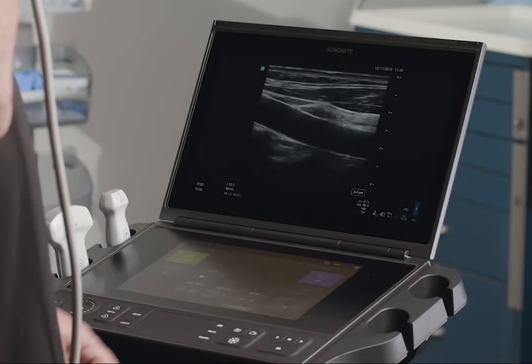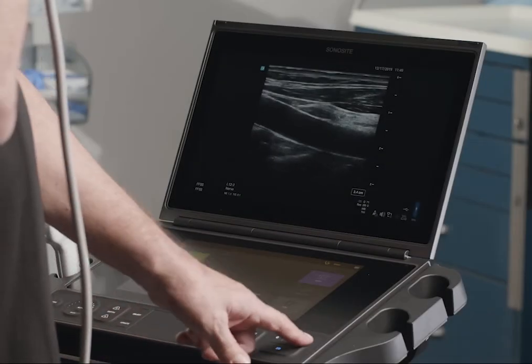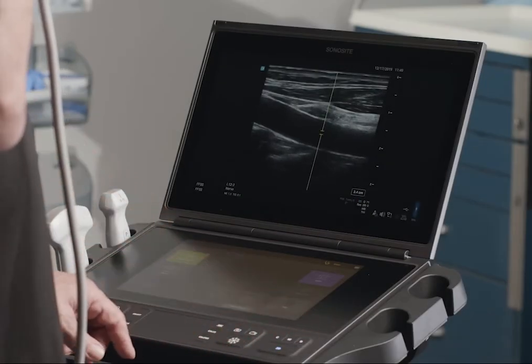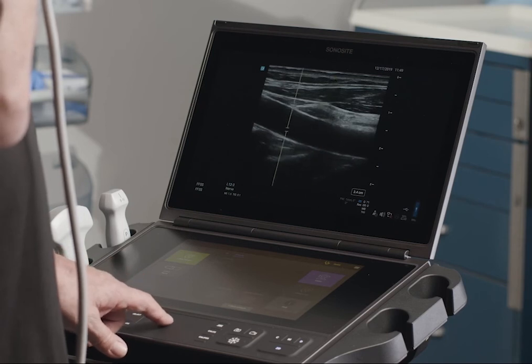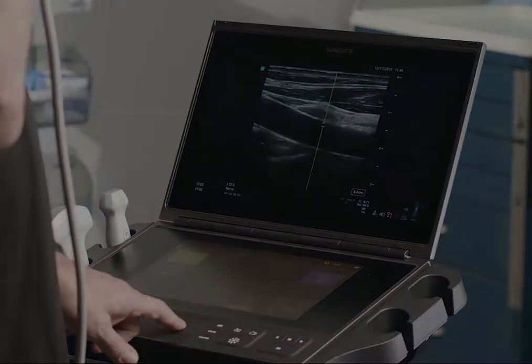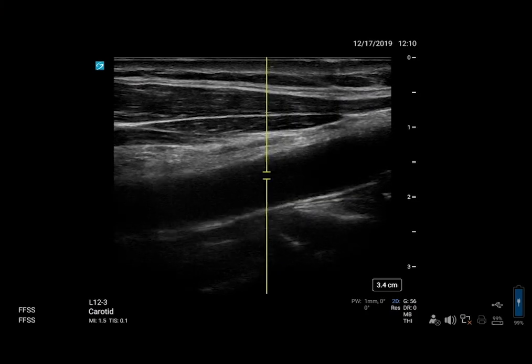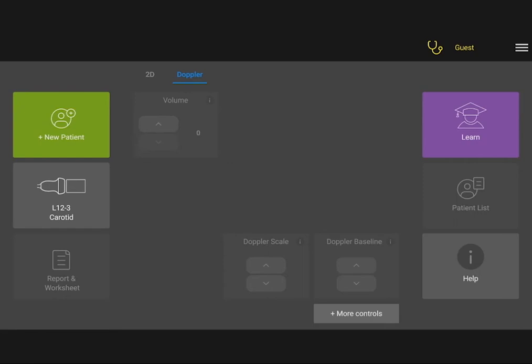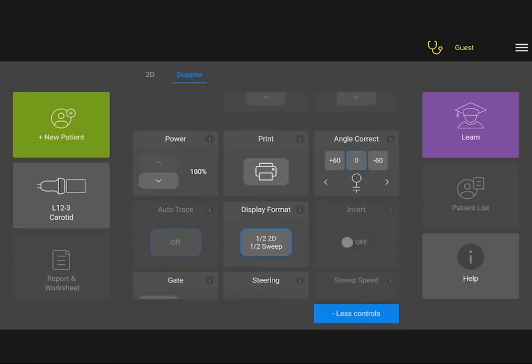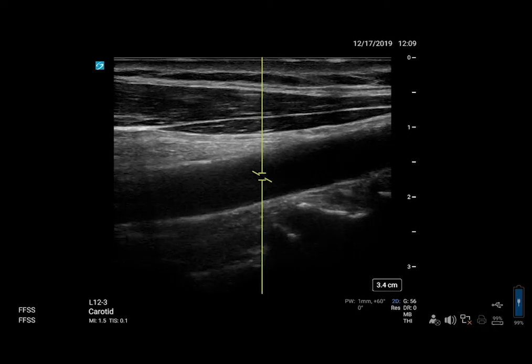Use the touch pad to position the D line and gate. Horizontal movements position the D line and vertical movements position the gate. To correct the angle of the gate, use the angle correct control on the touch panel.